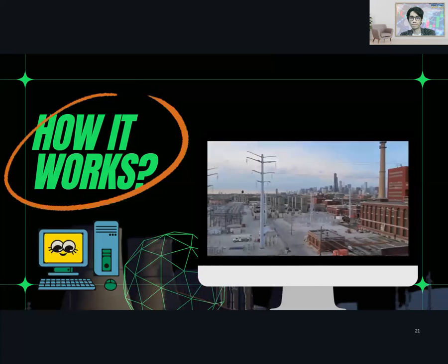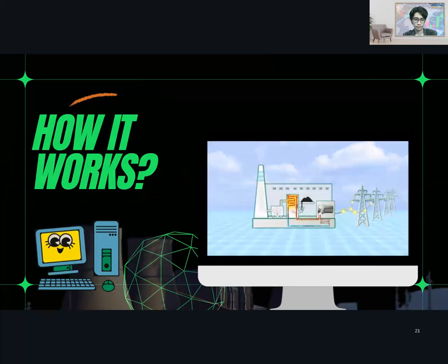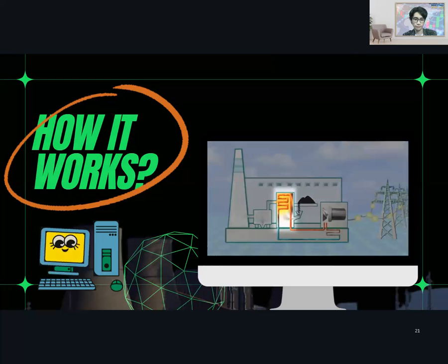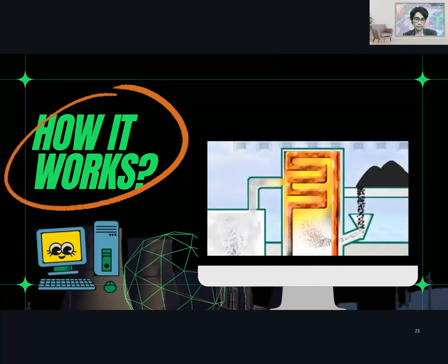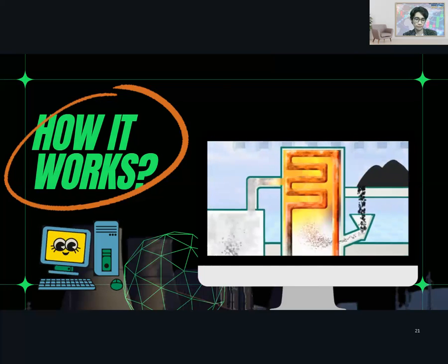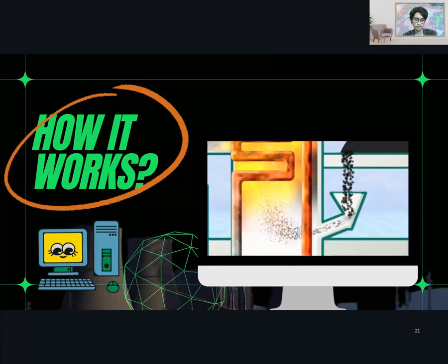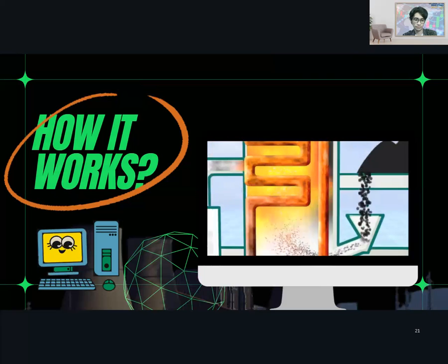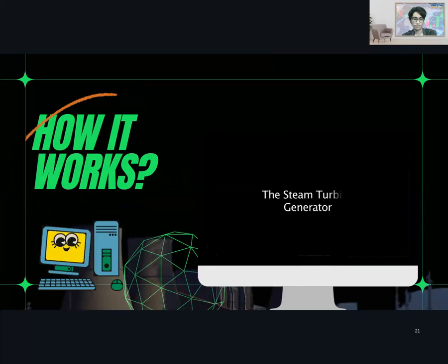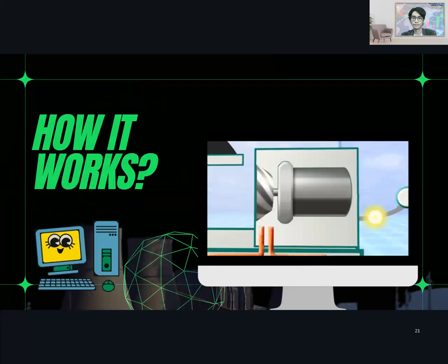Traditional coal-fired power plants like Fisk and Crawford have two basic components. The first is a furnace boiler, designed to burn coal and capture the resulting heat energy using a system of circulating water and steam. The process starts with the boiler, which is a furnace where combustion takes place. Pulverized coal is injected with a stream of air into the furnace in a continuous process through a device known as a burner. Burners ignite the coal and air mixture, creating a maximum amount of heat, as much as 1500 degrees centigrade. The second part of the system is a steam turbine generator, which converts the heat energy captured by the steam into electrical energy.